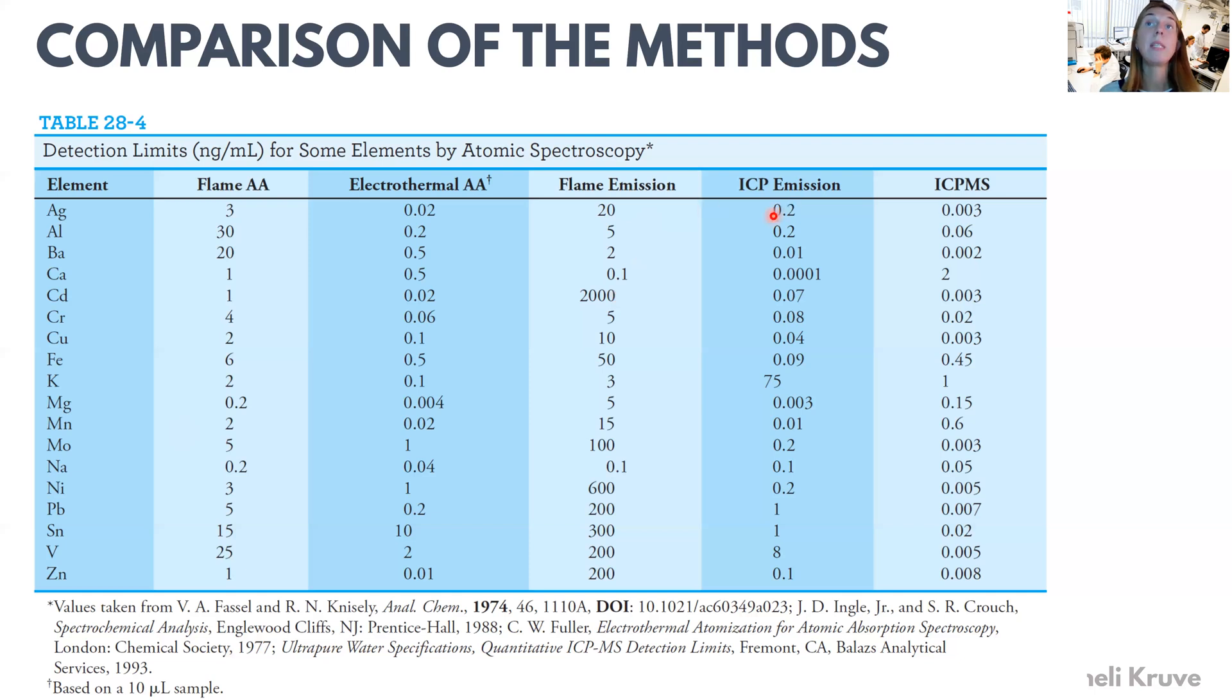When we now go to ICP emission spectroscopy, then we see that, depending on the element, the detection limits are much lower than they were for the flame emission, and they can also be much lower than they were for the atomic absorption with the graphite furnace. So ICP emission spectroscopy, of course, gives even better sensitivity for most of the elements, not all elements, but most elements.